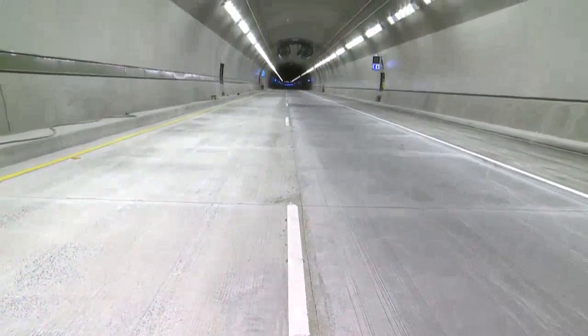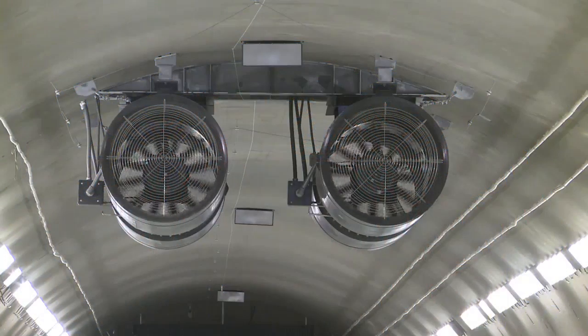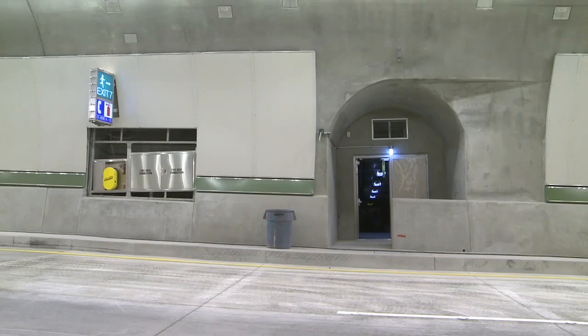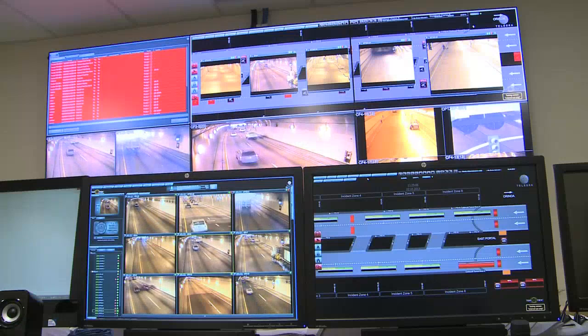The tunnel, complete with in-situ concrete lining and a plastic sheet waterproofing system, also includes 19 ventilation fans, brighter lighting, emergency exits along the length of the tunnel, and state-of-the-art fire and life safety systems. There are high-band radio systems, NOx sensors, and carbon monoxide sensors — if they trigger too high, the fans come on automatically. Cameras instrument the whole tunnel to monitor all corners and the seven cross passages cutting over into bore 3.